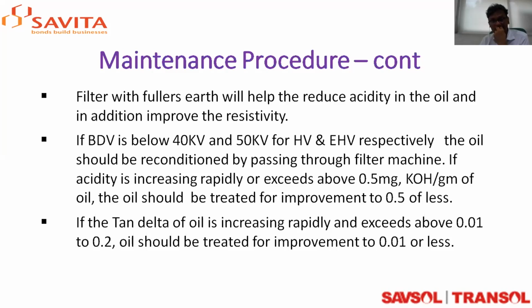That is most important. If the BDV of the oil goes below 40 or 50, one should think of reconditioning the oil. But before reconditioning, one has to check simultaneously the moisture of the oil as well as the acidity of the oil. If moisture is high and acidity is low, one can go for vacuum filtration, or if acidity is high, then one can go for the Fuller's treatment.